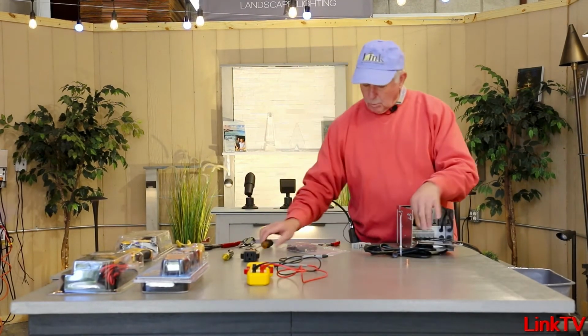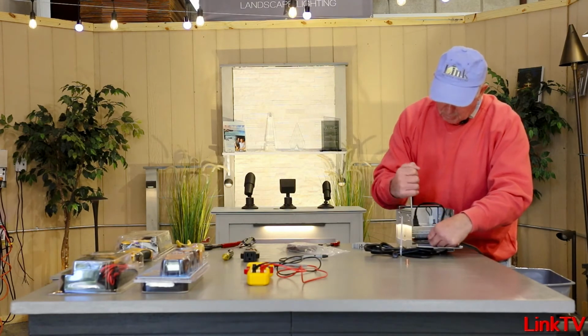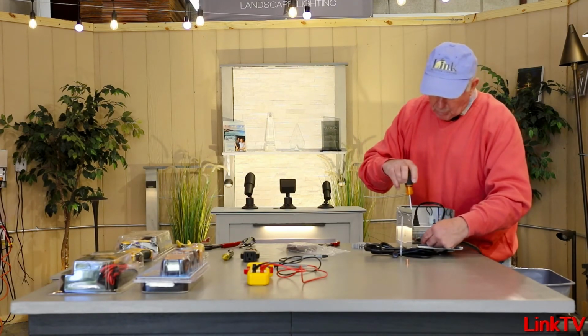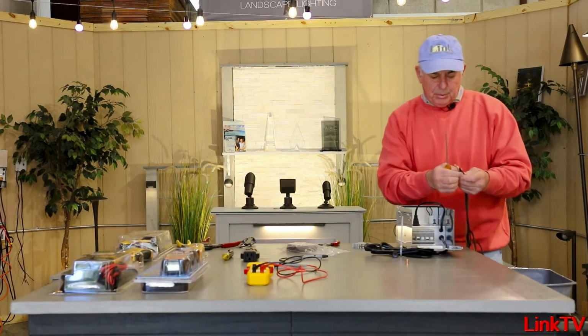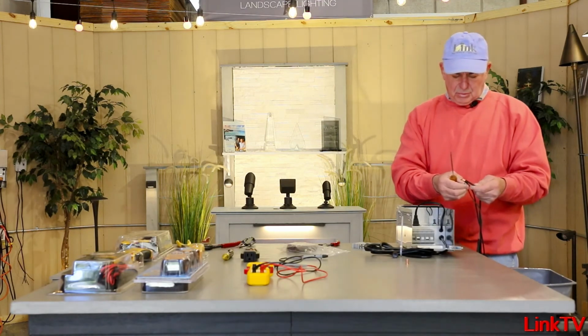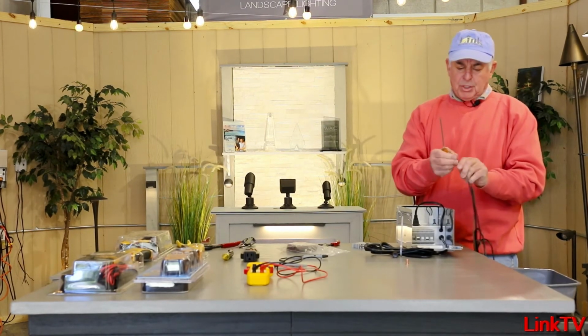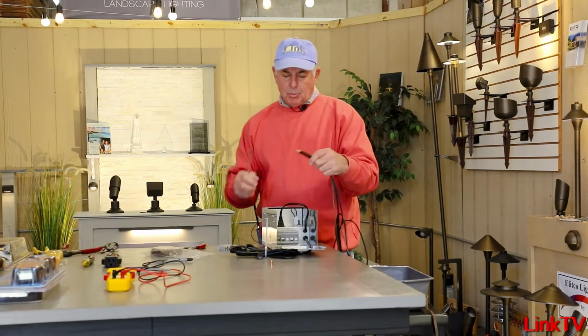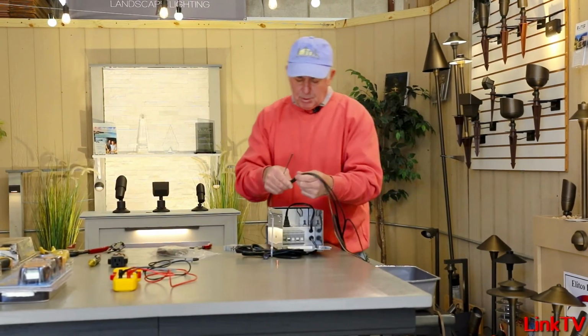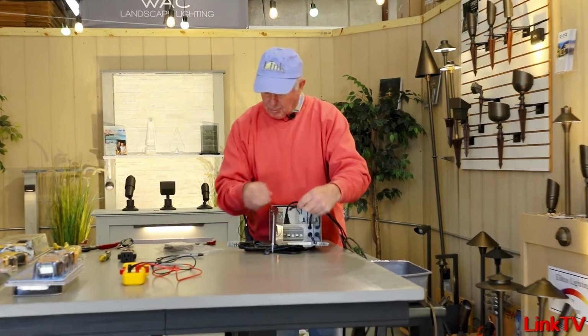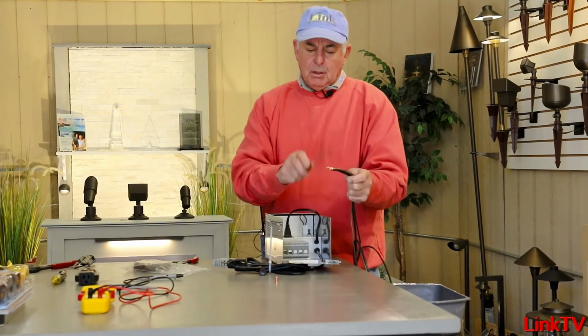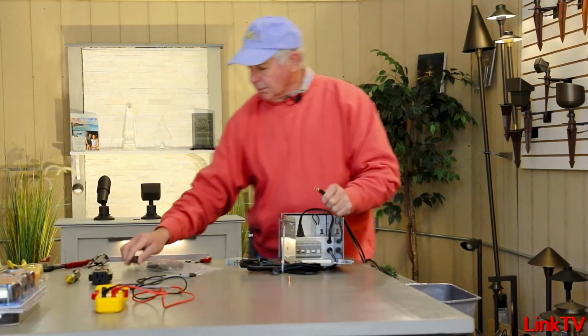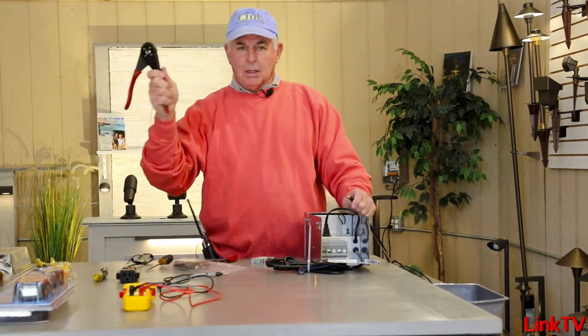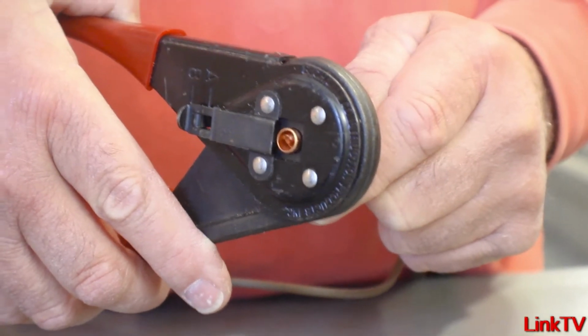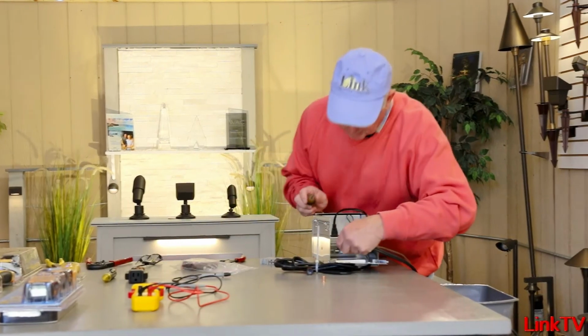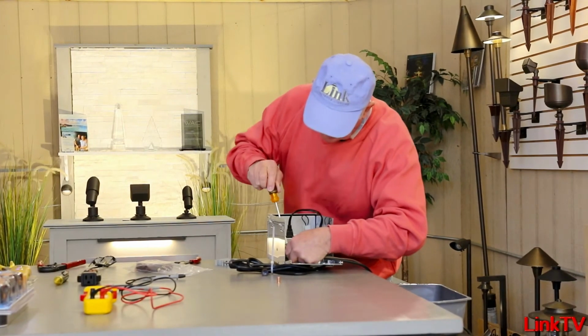So here's a little trick. All the wires going into common—this represents maybe a number 10, 16, or 14, just typical wires you'd put in a common on any transformer—put them together and copper crimp them. Remember our copper crimp tool? You can't live without it, or without copper crimps. Once you do that, you don't have any stray hairs, and you can put that in there.